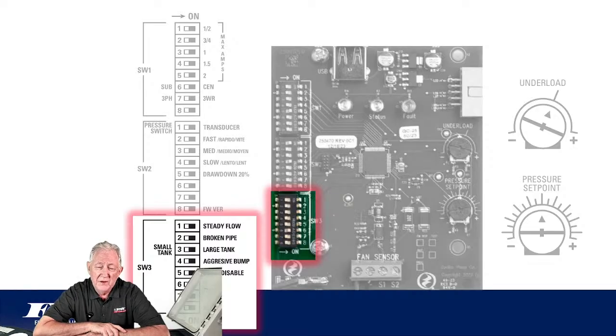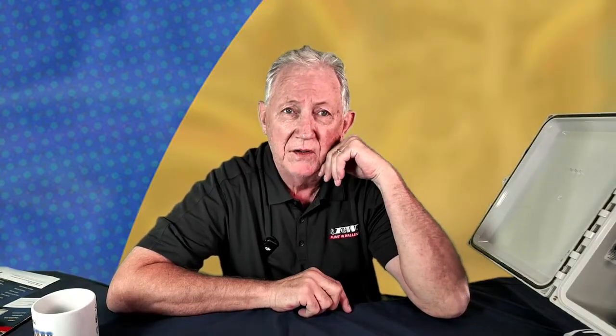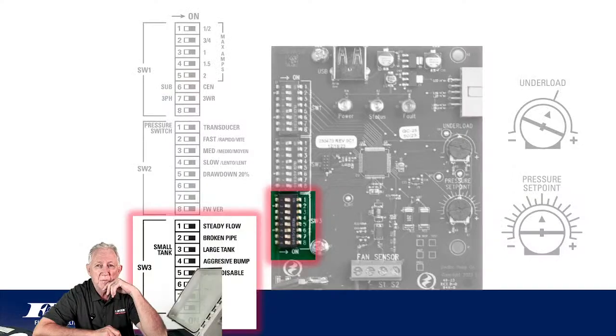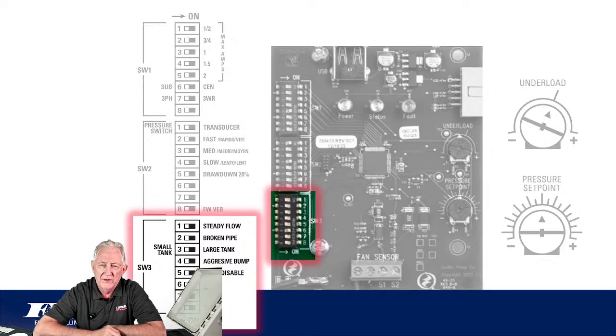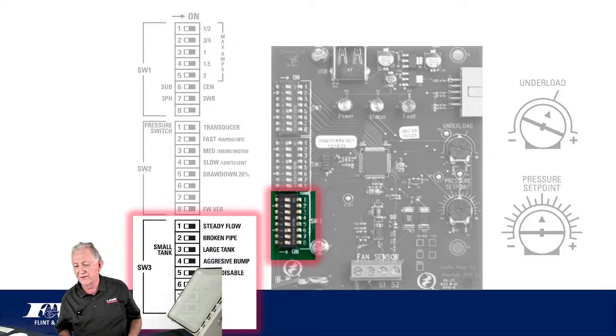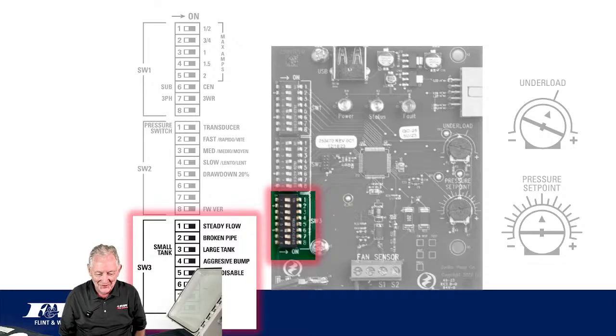If it's a brand new install, a drive doesn't need the size of pressure tank that a conventional water system running off a 20-pound pressure switch would need. A lot of these drives are installed with tanks not much bigger than a basketball, but therein lies your choice between a large tank and a small tank. We're going to get to a key word over here. Those two dials on the right, the top one is your underload and the bottom one is your pressure. Here's your key word for the day: set point, all one word.